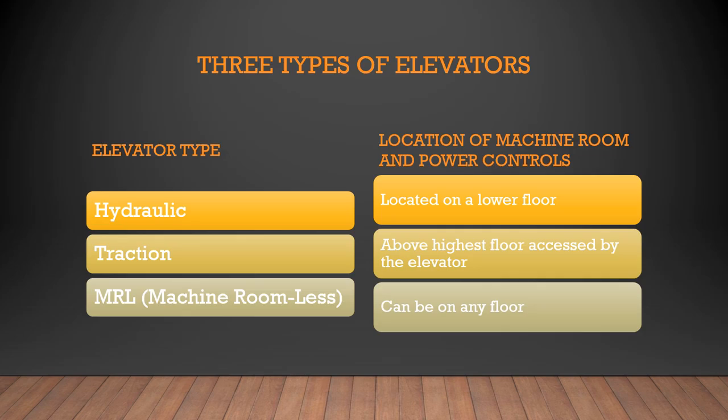There are three types of elevators: hydraulic, traction, and MRL or machine roomless. The important part is to understand the location of the elevator machine room and the power shutoffs. For hydraulic elevators, the machine room is on a lower floor next to the elevator shaftway. For traction elevators, the power shutoffs are in a machine room above the elevator shaftway at the highest level. For MRL, because the motor is located in the shaftway itself, there's no elevator machine room, so the power shutoff is typically in an access panel near the elevator but can be located on any floor.